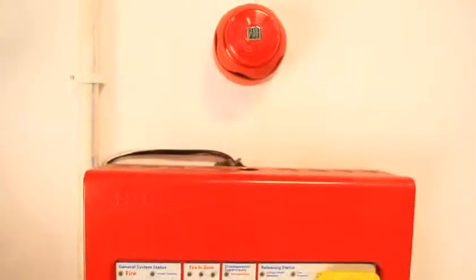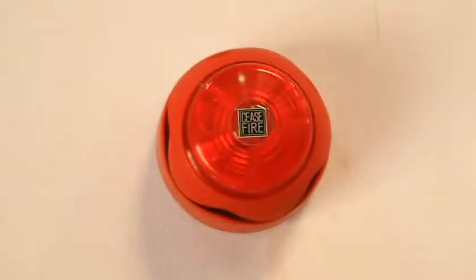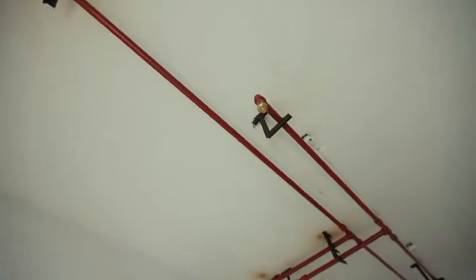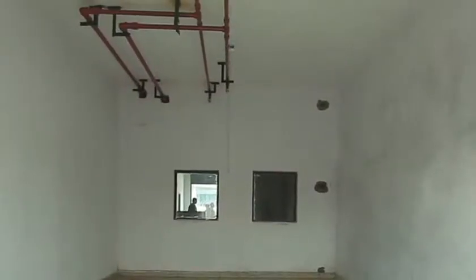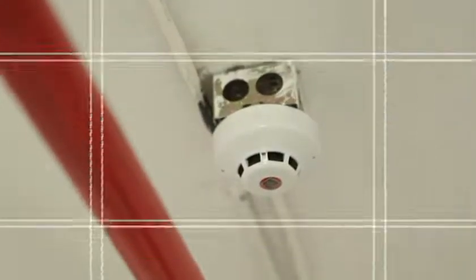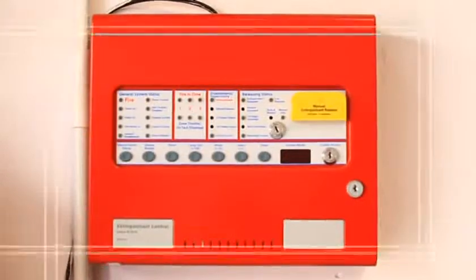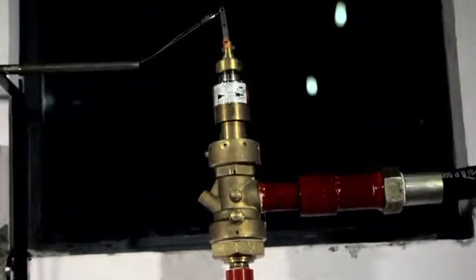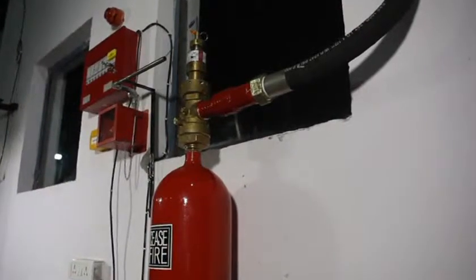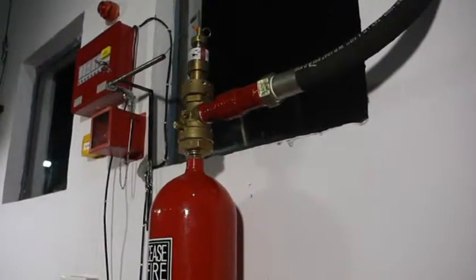Harnessing the latest in cutting-edge firefighting technology, the FM-200 suppression system has been specially designed for commercial enterprises and industries. The entire system is made up of various detectors, discharge nozzles, alarm sounder, control panel with automatic release, and a facility for manual release, and of course the cylinder valve with FM-200 agent.